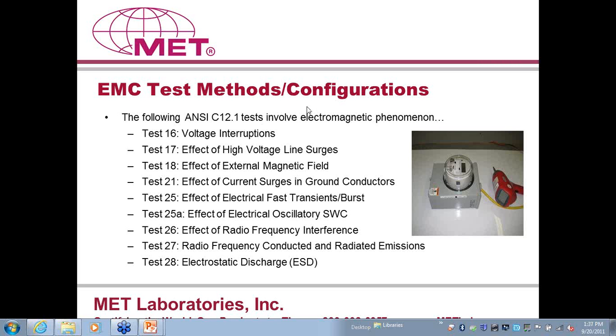Then there is test number 21, effect of current surge in ground conductors. This test subjects the meter to very strong magnetic impulses, which somewhat simulates the effect of an indirect lightning discharge. Then there's test number 25, electrical fast transients. These are repetitive electrical transients or disturbances that originate due to switching transients or inductive loads.